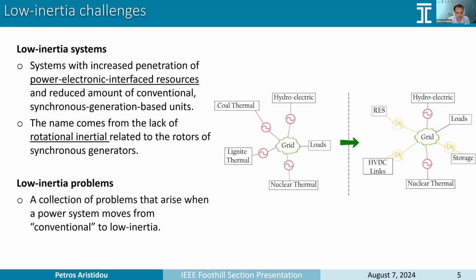And when we talk about low inertia problems or low inertia challenges, we're talking about the collection of problems that arise when a power system moves from a conventional power system to a low inertia power system. These problems are not only related to the lack of rotational inertia in the system, but it's a more general term that catches different problems that come from shifting from a conventional system to a low inertia system.